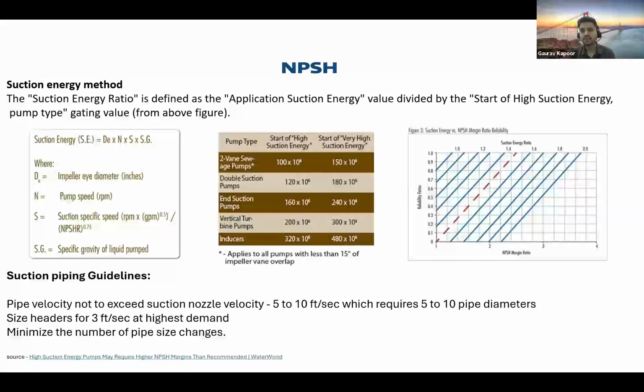Cavitation is a very, very common factor which we have seen in district cooling plants across the globe. In the last 5 years, when we started doing this calculation of suction energy ratio and improved the NPSH-A to NPSH-R ratio to 3 or 4 times, all of those issues have gone away, and the life of the pumps has gone very high.